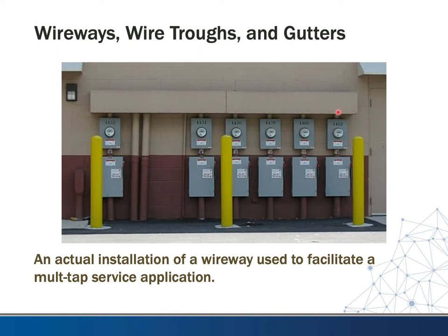And then we tap off those conductors, go through the meter, then go through the disconnect. So this is your main disconnect. And so this is your 10-foot span. We're within 10 feet, so we have a fused disconnect. And then they go underground to feed the separate store locations.